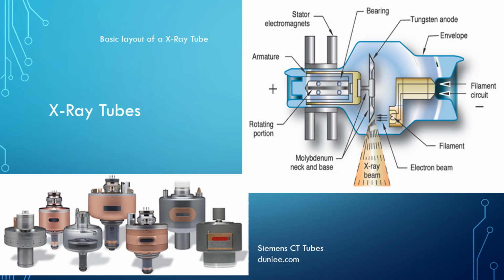The other things that you have here, the armature and the rotating portion, are really there to support the anode, as well as the bearings and the stator electromagnets. And this whole part here is called the glass envelope.